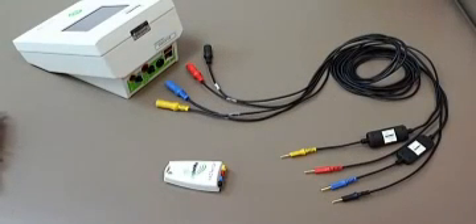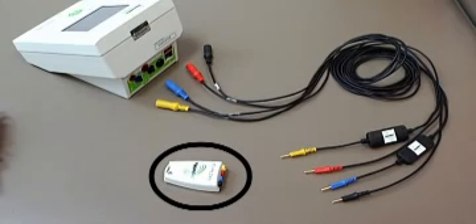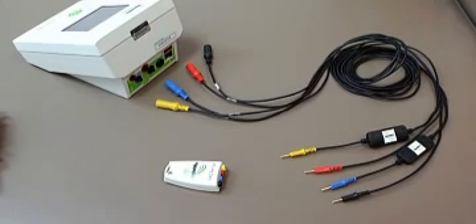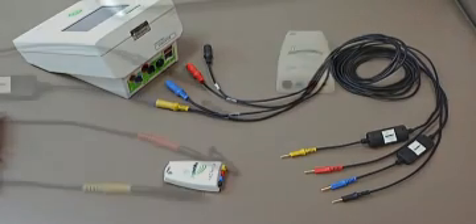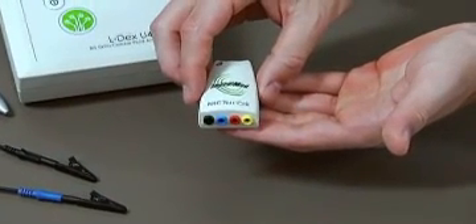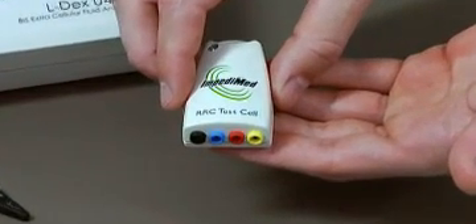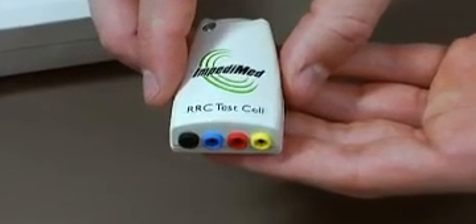The first thing you will want to do before taking your first measurement with the U400 is verify that the device and leads are working properly. This is done using the test cell provided in the soft carrying case. Calibration of the U400 is set by the factory during the manufacturing process. An RRC test cell is included as part of the complete U400 kit. The test cell helps to validate that the device is operating within its calibration specifications.